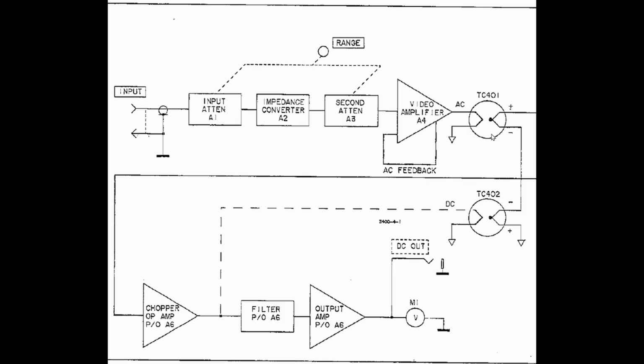Now what that does is this: it takes care of a couple issues. One is thermocouples are not linear, so we could not get a linear output from here. But if we do this, because this one's linearly going to move the opposite direction, we can take the two outputs and get a linear output from them.